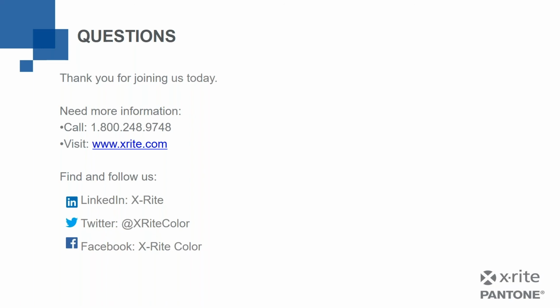But what NetProfiler offers you is ensuring your instrument in your environment is functioning properly. Remember that slide I showed where the instrument varied greatly during the year? Over 6 years, we saw a peak every summer. So it's about the instrument being profiled for where you're using it.